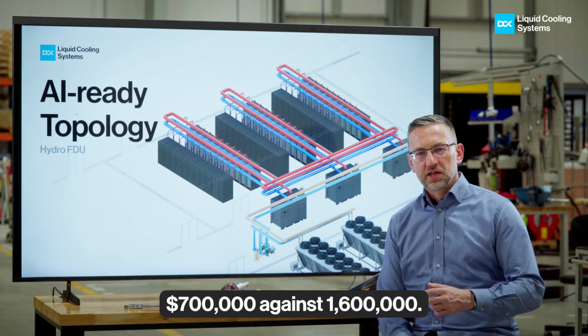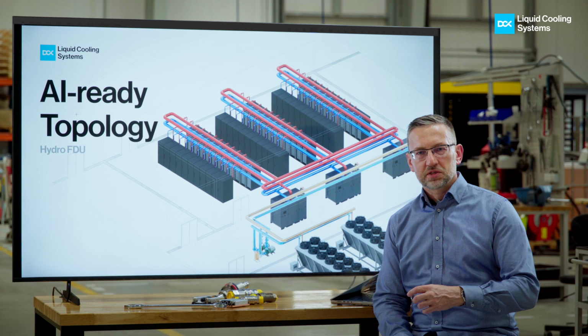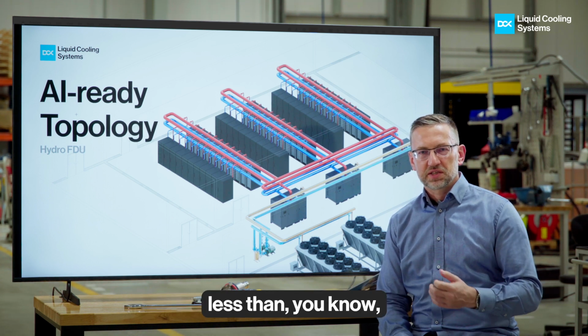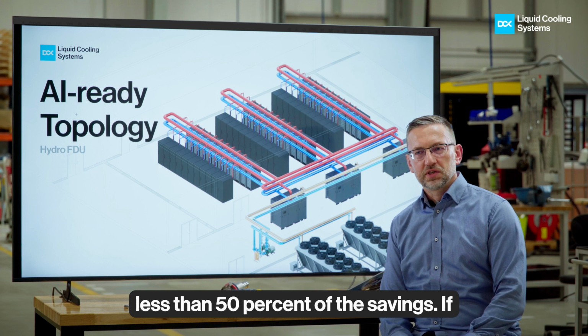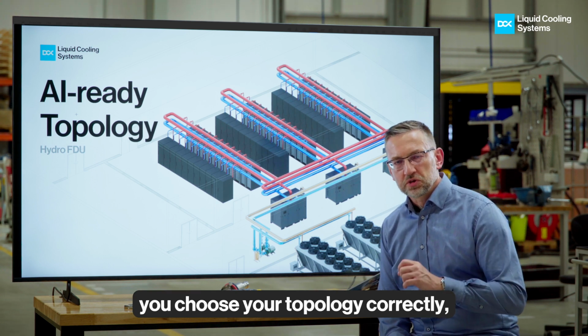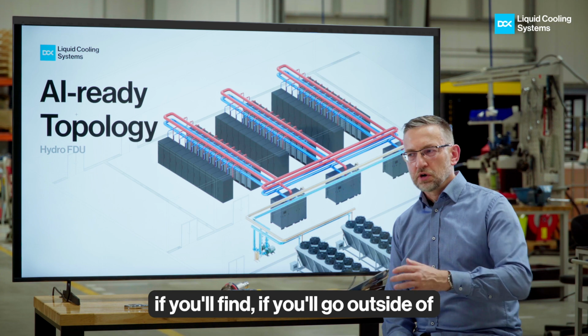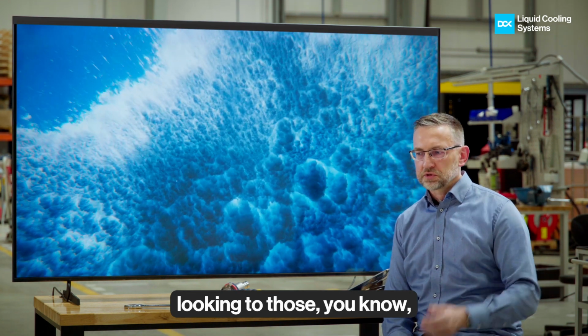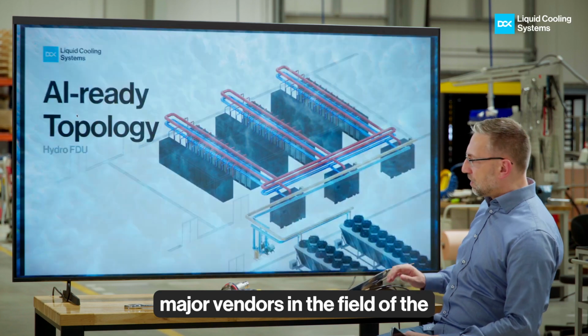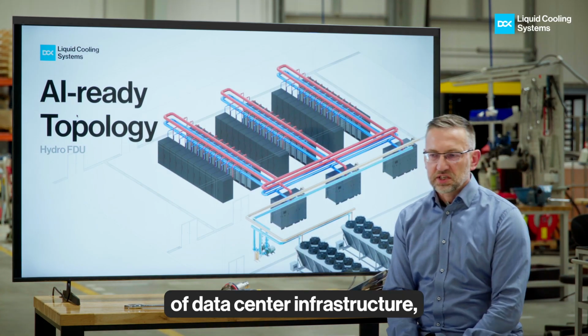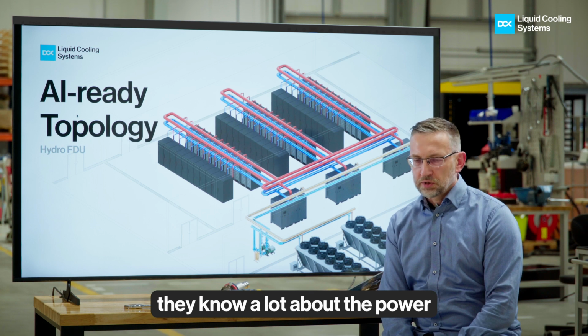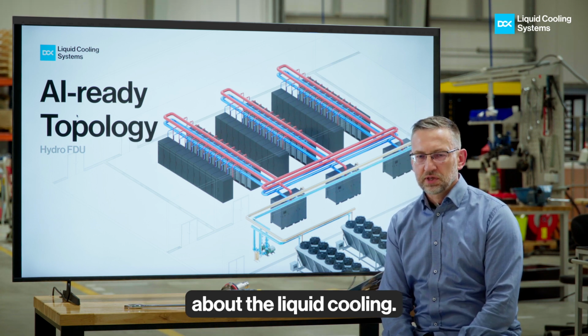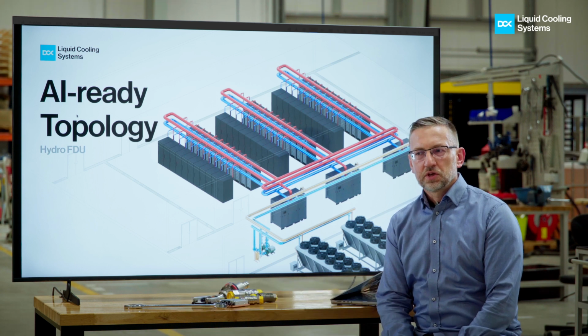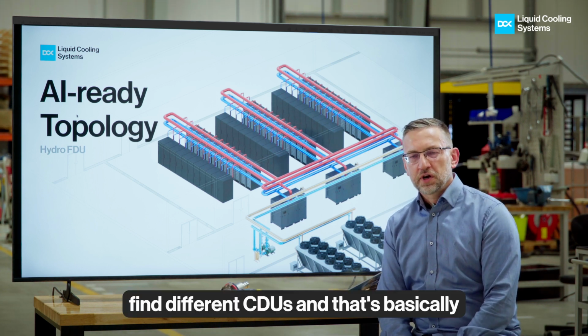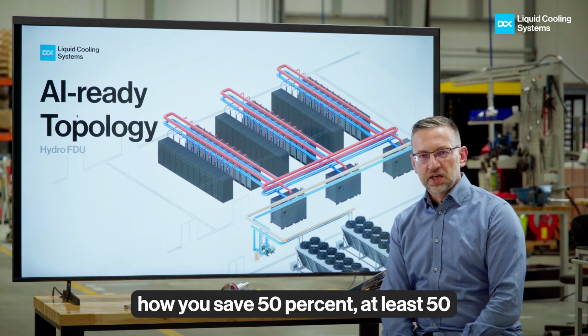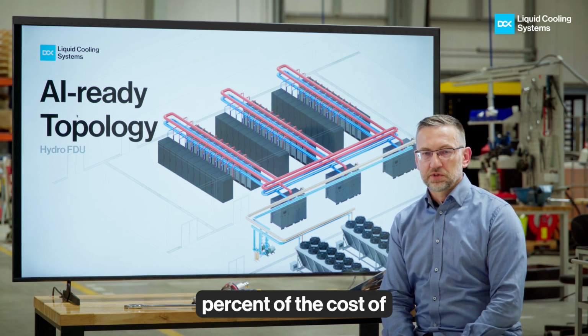So it's $700,000 against $1,600,000. So it's twice less expensive, right? It's less than 50% of savings. If you choose your topology correctly, if you go outside of the box, instead of just looking to those major vendors in the field of data center infrastructure, they know a lot about the power distribution, but they don't know much about the liquid cooling. Look outside of the box, look for the solutions, find different CDUs, and that's basically how you save at least 50% of the cost of the liquid cooling system.